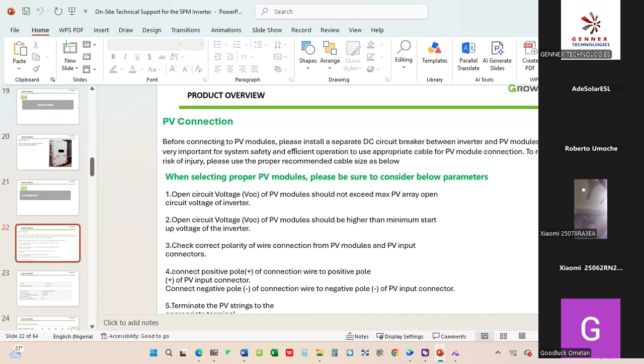Then when selecting the PV cables and the PV wattage, it's always encouraged to take into consideration the open circuit voltage of the panels. Then also check the correct polarity wiring of the PV, because this inverter has a positive and negative terminal. So when connecting your PV to the inverter, don't put the negative cable on the positive side and the positive cable on the negative side. It's going to affect the MPPT of this inverter. So whenever you are connecting your cables, always make sure you take into consideration the polarity of the PV cable, the positive and the negative.